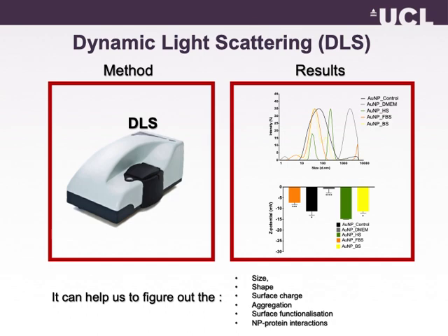Dynamic light scattering, DLS, is one of the widely used techniques for the analysis of nanoparticle-protein interactions, as well as surface functionalization, aggregation, surface charge, shape, and size of your nanoparticles. DLS tells you about the hydrodynamic diameter of your nanoparticles, meaning it picks up the core bare nanoparticles surrounded by a water shell. It is therefore better to use TEM for core size analysis and DLS for particle size analysis inside water or serum.